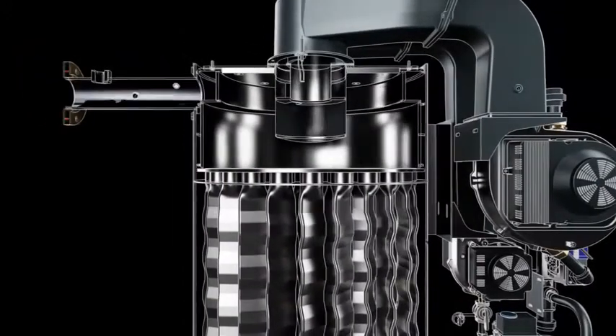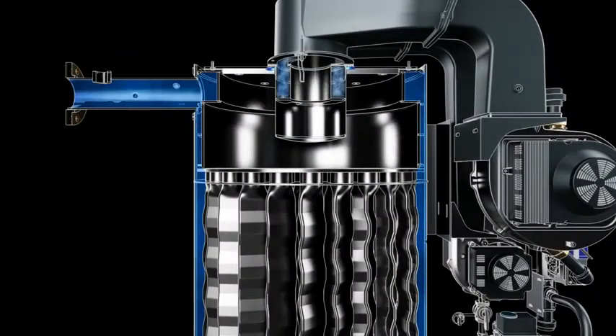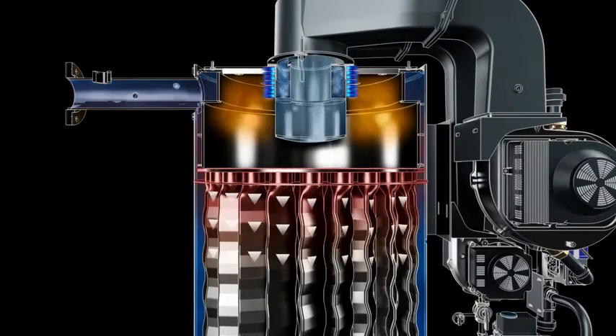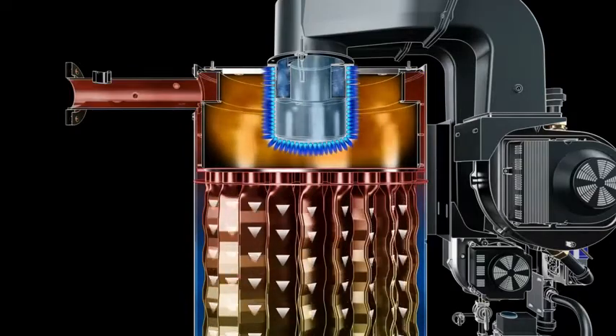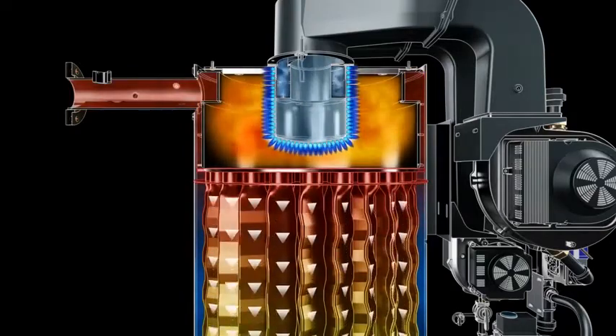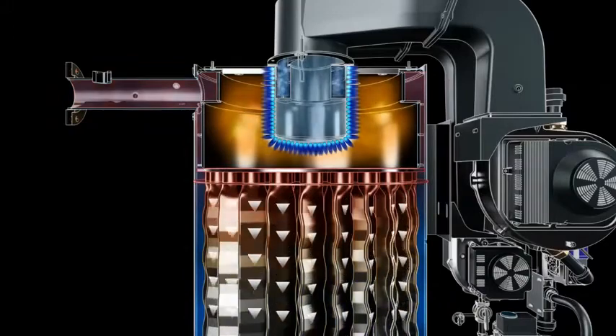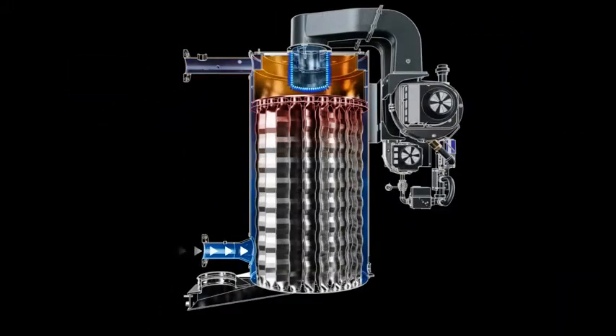In a 2 million BTU CREST, the burner can operate with up to 25 to 1 turndown, firing as low as 80,000 BTUs, modulating with demand up to 2 million BTUs, and reversing the sequence for shutdown. No other fire tube boiler can match CREST for turndown and total system integration for dependable operation and efficiency.